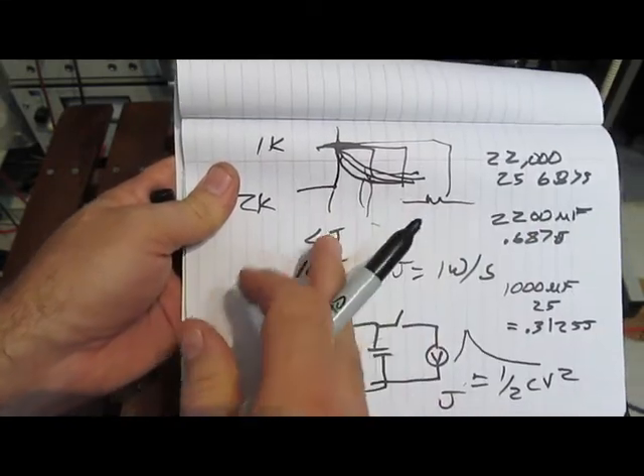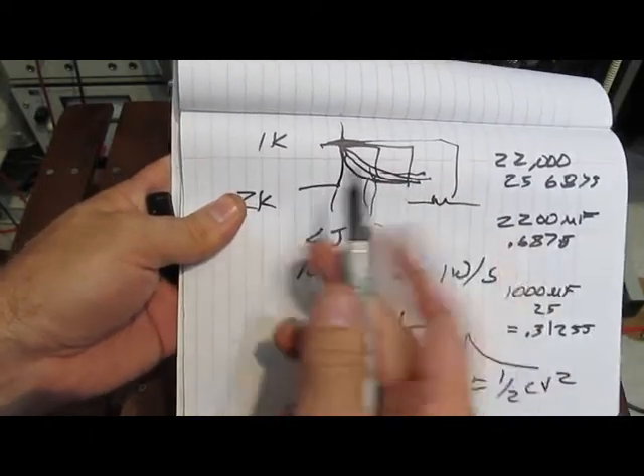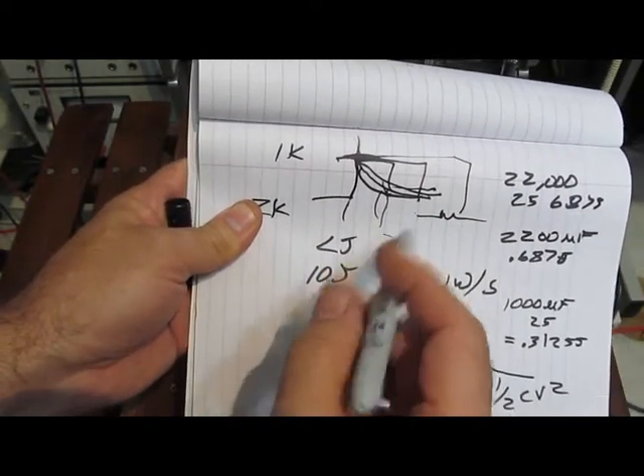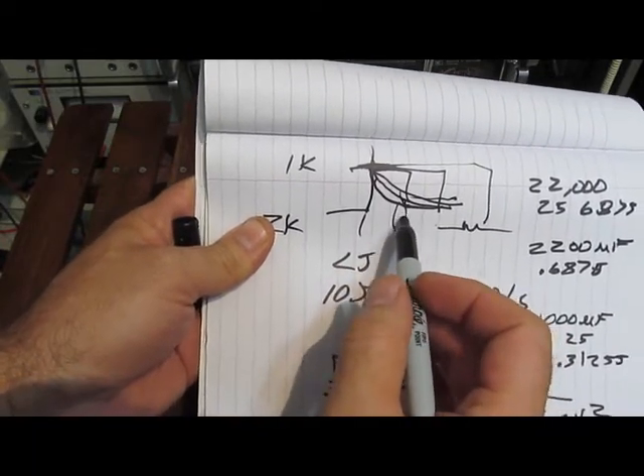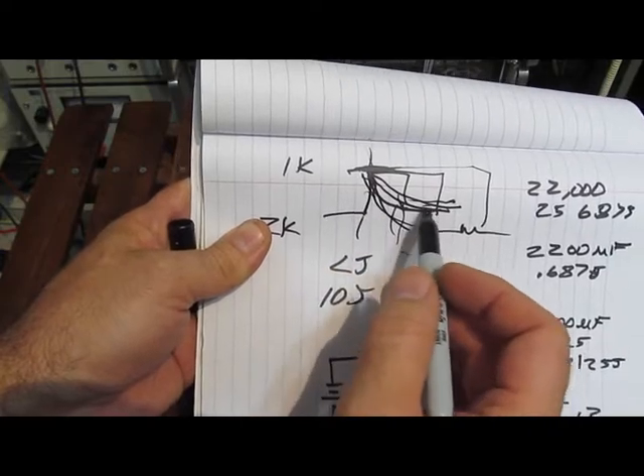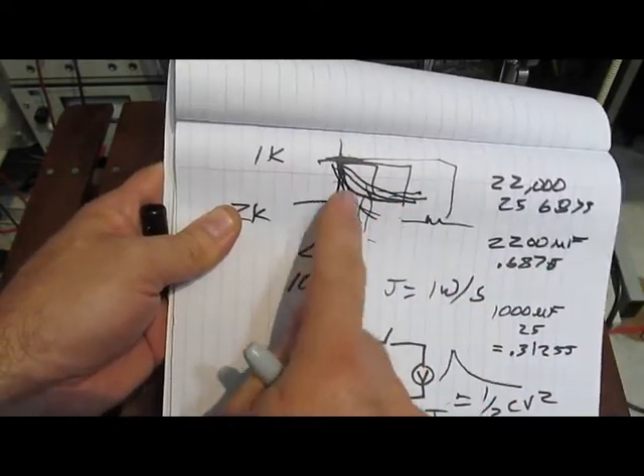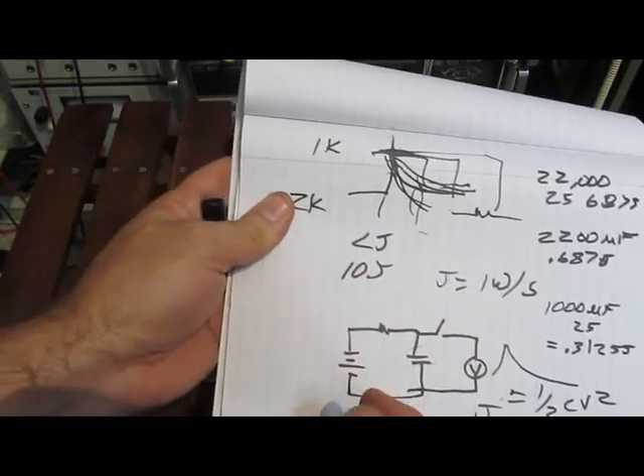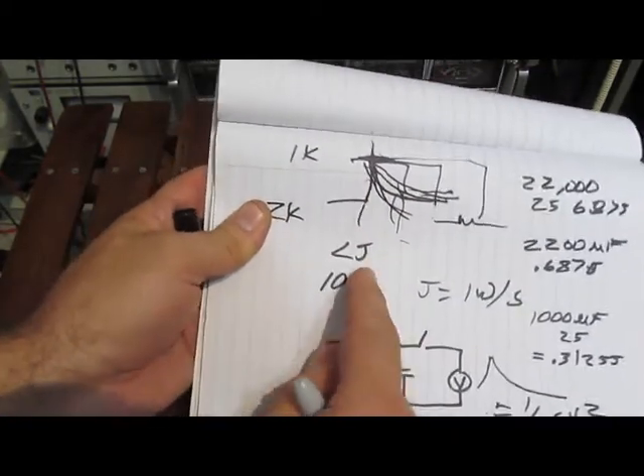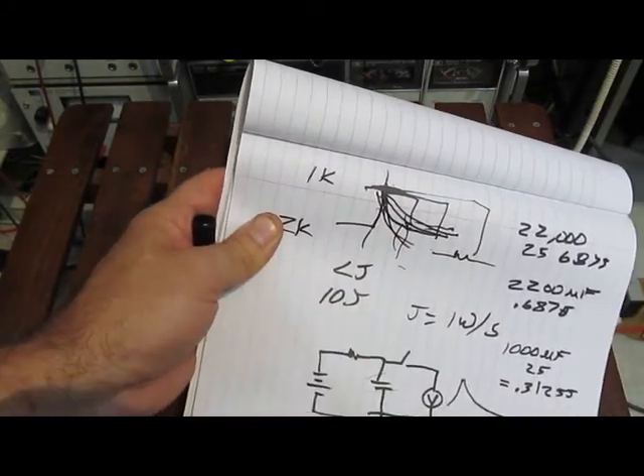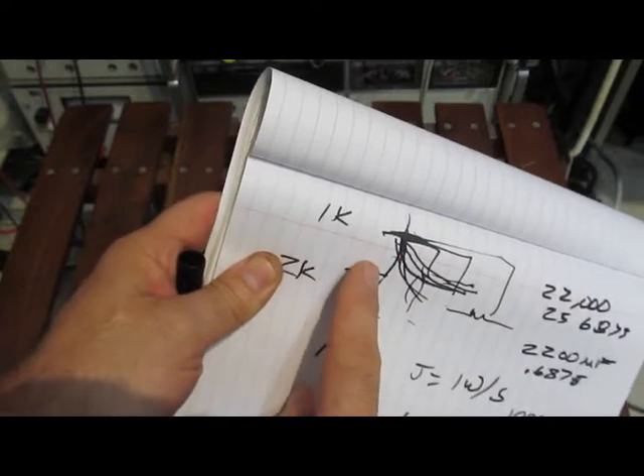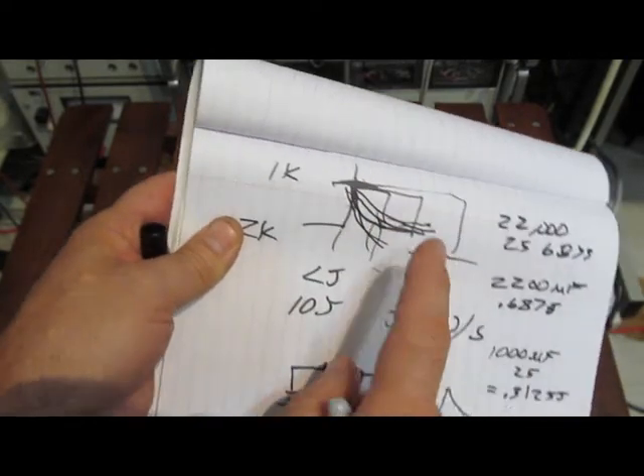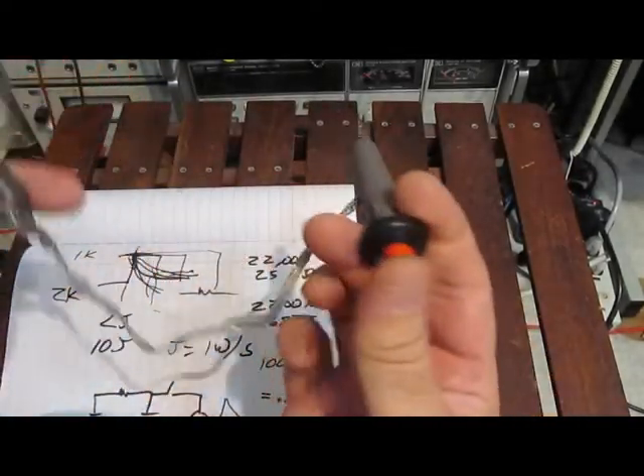So what I've done in the past is I kept that full width half-height very constant and I increased the voltage. But I could have gone this way with it as well. What I was trying to do is find how robust the meters were. There isn't really a way to do that that I'm aware of, a standard way to do that. So I chose the IEC standard, kept that waveform roughly the same shape and just increased the amplitude. But I limit the amount of energy. So if you look at a waveform generator like that, they're typically a combo generator. It's rated for a certain open circuit voltage and a short circuit current. What I'm doing is I'm using the open circuit voltage to define the waveform and I limit the amount of energy available.